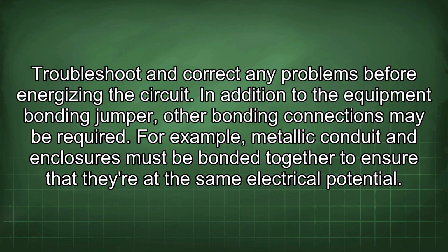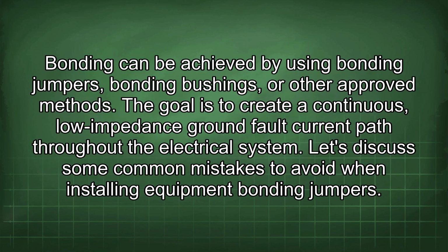In addition to the equipment bonding jumper, other bonding connections may be required. For example, metallic conduit and enclosures must be bonded together to ensure that they are at the same electrical potential. Bonding can be achieved by using bonding jumpers, bonding bushings, or other approved methods. The goal is to create a continuous, low-impedance ground fault current path throughout the electrical system.